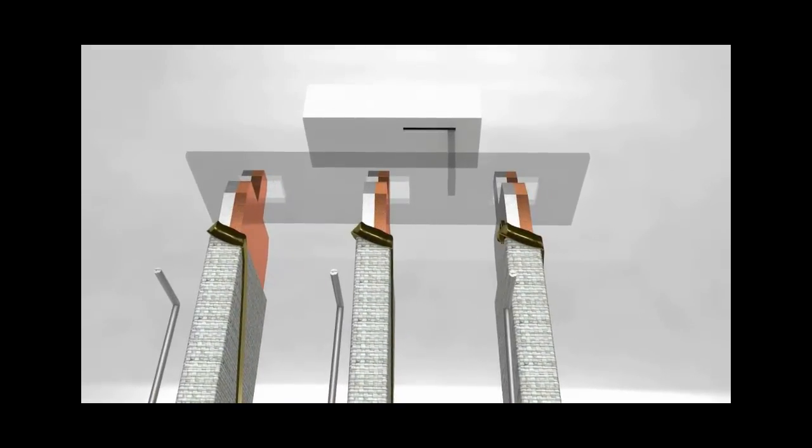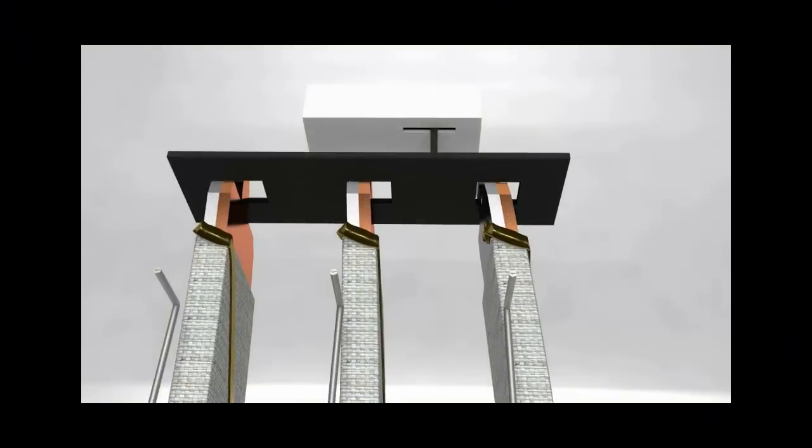When it bends, it moves the black piece called a trip slide that is connected to the trip unit. Once it moves the slide a certain distance, it trips, and the normally closed opens and the normally open closes.